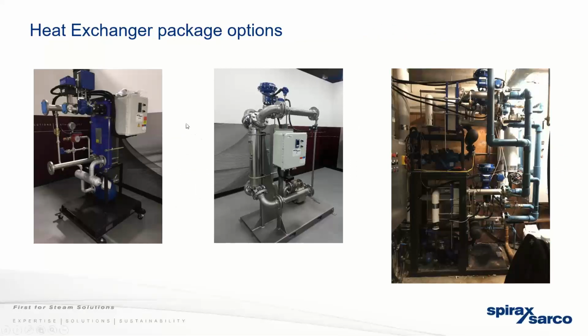Different package options. There's plate and frame like we've seen. We make packages as well with helical coil, also operating under vacuum. You can see the pump trap in the background there. You'll still see the high limit shut off and the tempering valve, so all those safety features are on there. The picture on the right may be a little hard to see, but it's two packages stacked on top of each other. There was a tight mechanical room, tight space required, and they still needed these, which probably look like 50 GPM units. So they stack them up just to save space.